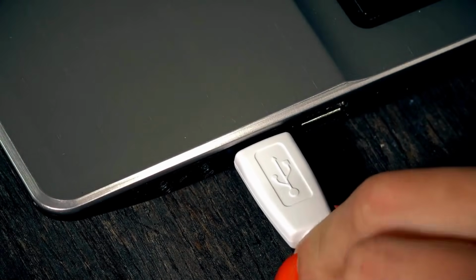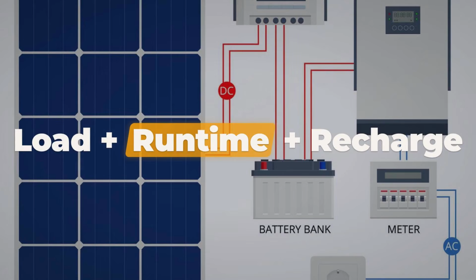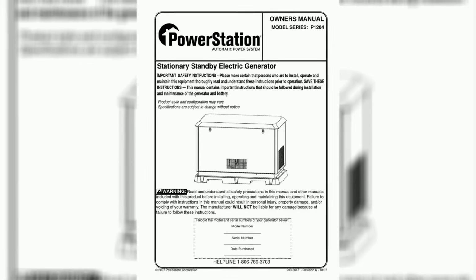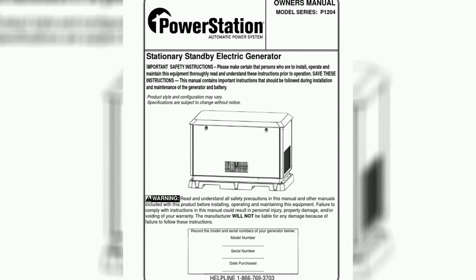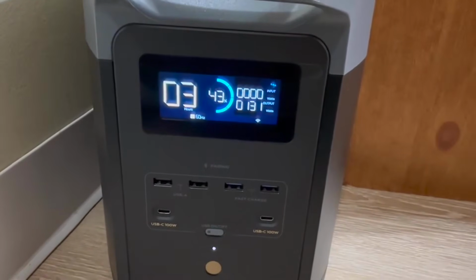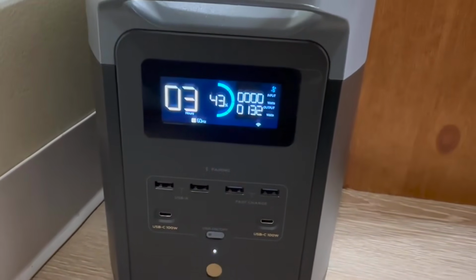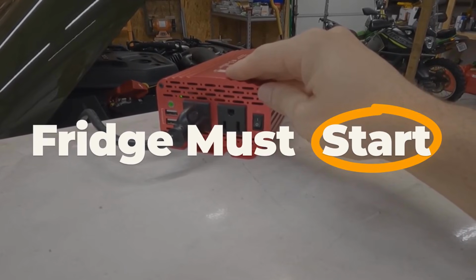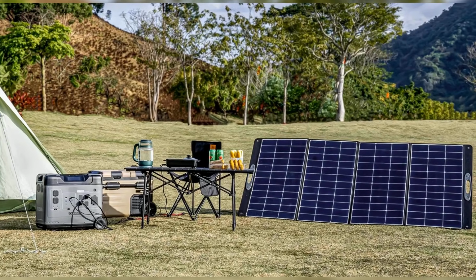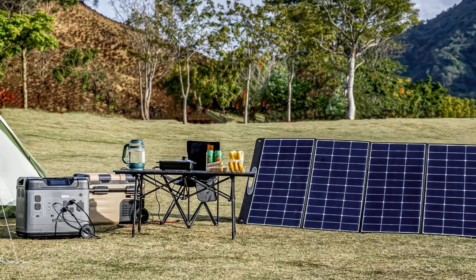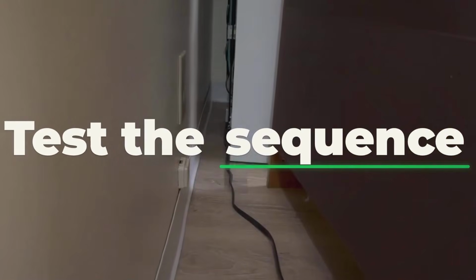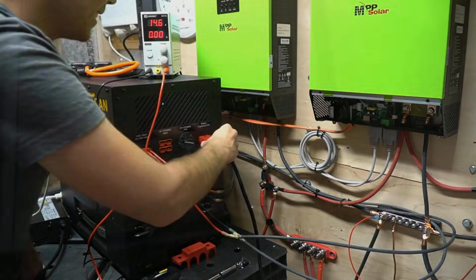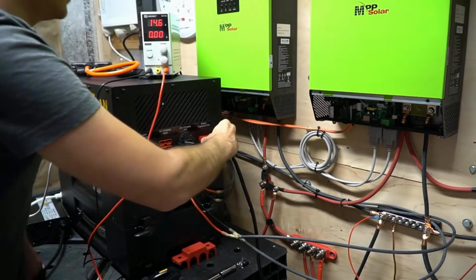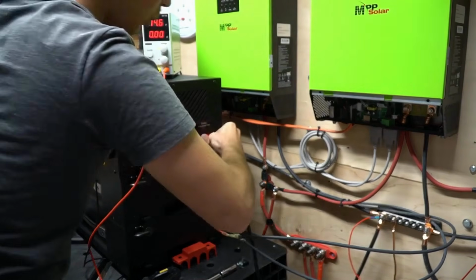So here is the rule that replaces every spec sheet comparison you will ever do. Backup equals load list plus runtime plus recharge plan. If any one of those three is missing from a kit's documentation, that kit has not proven it can protect your fridge. Not a caution, a disqualification. The concrete test is this. The fridge must start, run overnight, and the battery must recover the next day under realistic sun. All three in sequence, with your actual panel, your actual cable, your actual inverter. Not peak ratings. Real conditions.